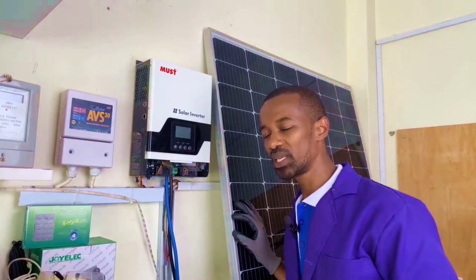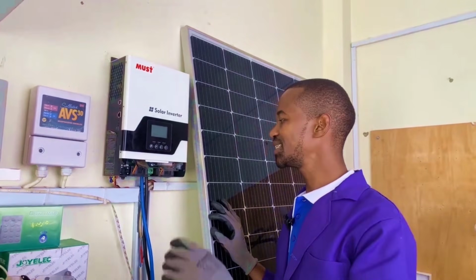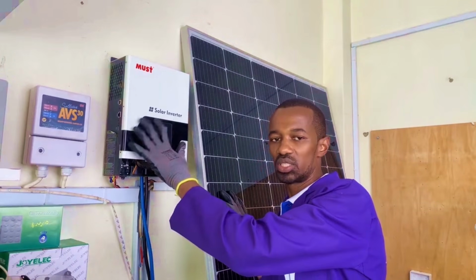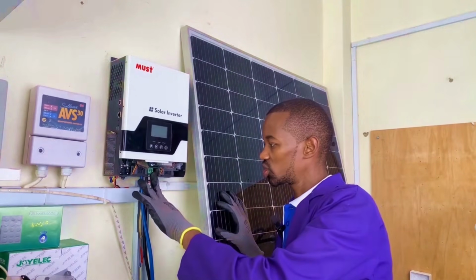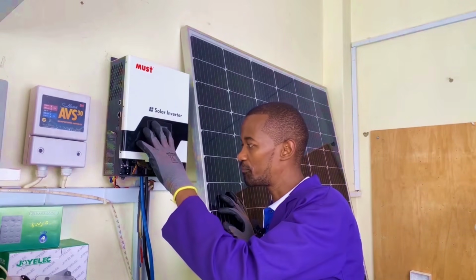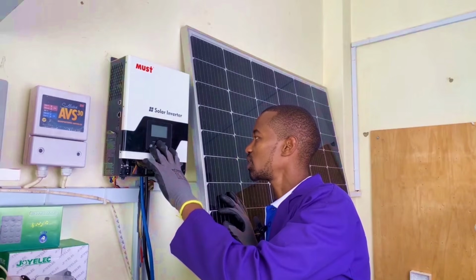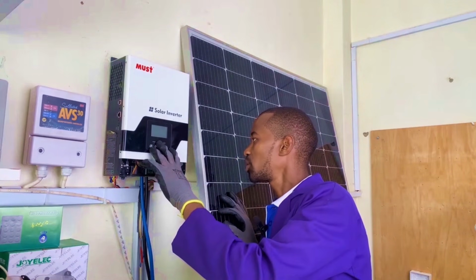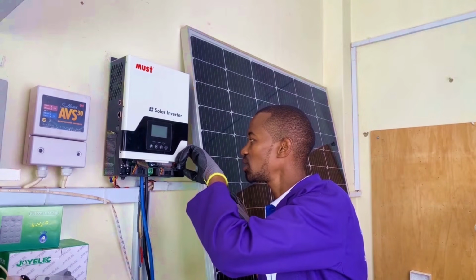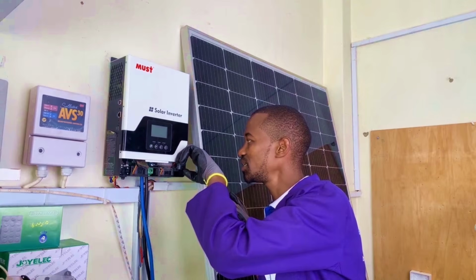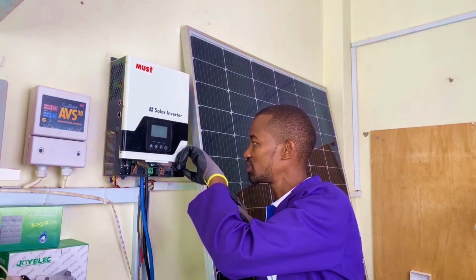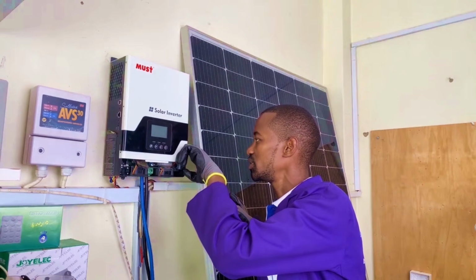Another mistake that people commit, which is number 4, is definitely when sizing up this system, they use the wrong voltage from the battery. If this is supposed to be a 12 volt inverter, don't connect a 24 volt battery, because this inverter is indicated on the side. It is a 12 volt DC system, or the system voltage should be 12 VDC. That means 12 volt DC.